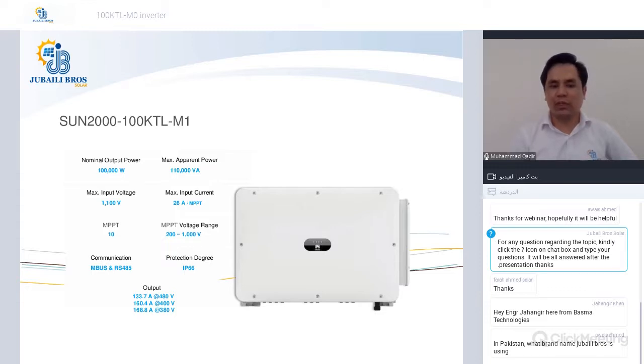Maximum input voltage of this inverter is 1100 volt, but we recommend that your open circuit voltage should be within 1000 volt, and due to the temperature variation, if this voltage goes beyond 1000, the inverter can accept up to 1100 volt in that case. Maximum input current is 26 ampere. With the previous inverters, Huawei used to have 22 ampere, such as the 50 and 60 kilowatt inverter.